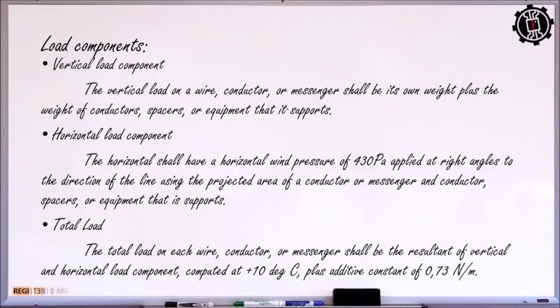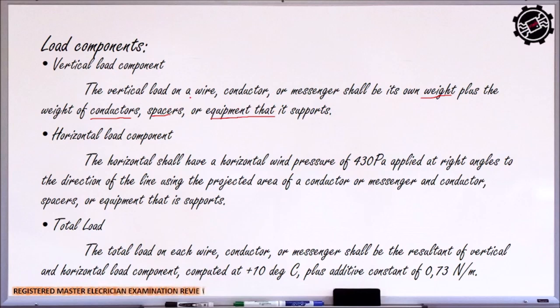So, ito yung nagpo-push sa ating wire to move downward or para magkaroon siya ng sag. No? So, the vertical load component of a wire, conductor, or messenger shall be its own weight. No? Yung kanyang bigat. So, as the wire increases in its size, tataas or magi-increase din yung kanyang weight, plus the weight of the conductors, spacers, and the equipment that it supports. So lahat ng component na nasa ating linya, so all of the weight of that one will be considered as part of the vertical load.